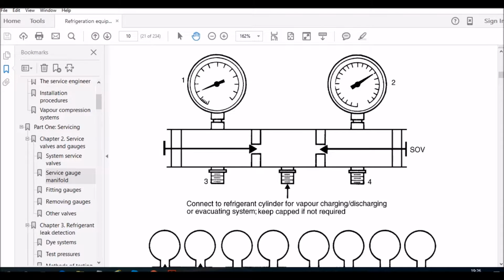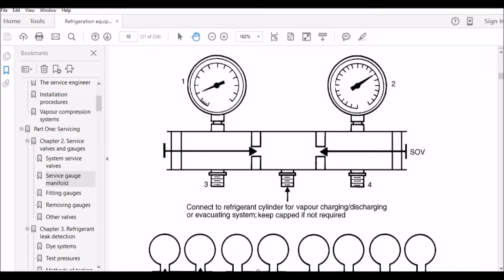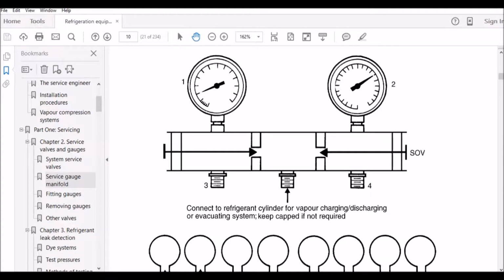And again, what we're seeing here is the low side gauge manifold represented with number 1, and the high side gauge manifold represented as number 2. Number 3 is where you would connect your low side hose. This one here with the arrow is where you actually connect your yellow service hose. Your service hose is usually connected to your refrigerant bottle for charging up the actual system, or it can be connected to your vacuum pump for vacuuming out the system, or it can be connected to your nitrogen gauge for pressure testing an empty system.